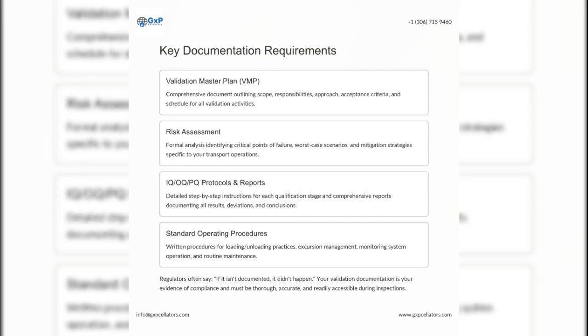Validation requires comprehensive documentation, including a master plan, risk assessment, IQ, OQ, PQ protocols, and standard operating procedures. The master plan outlines scope, responsibilities, and schedule. Risk assessment identifies critical points of failure and mitigation strategies. Protocols detail each qualification stage, and SOPs provide routines for loading, execution management, and routine maintenance. Regulators often say, if it isn't documented, it didn't happen. Your validation documentation is your evidence of compliance and must be thorough, accurate, and readily accessible during inspections.